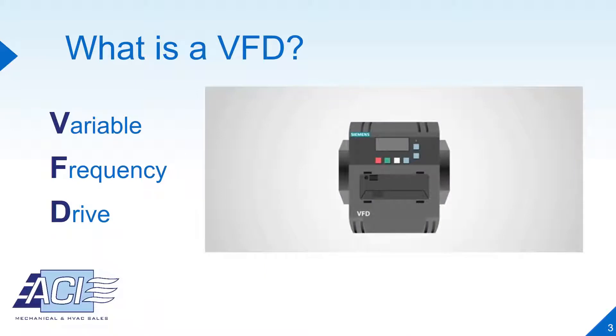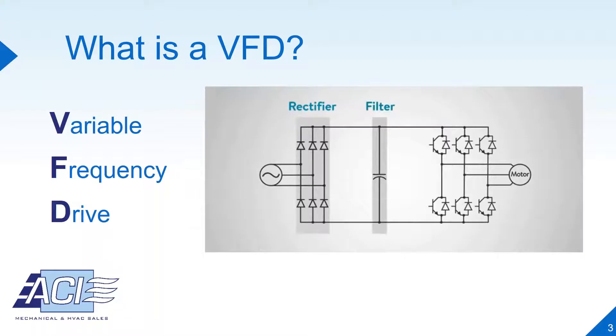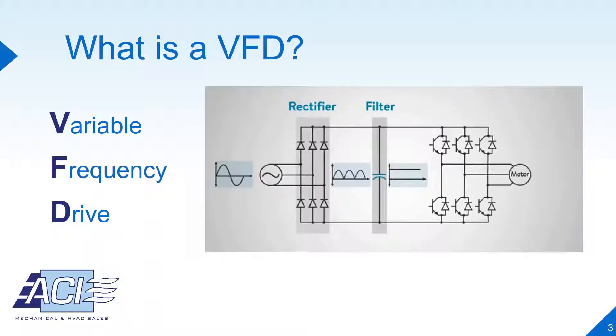What is a VFD? VFD stands for Variable Frequency Drive, and it is an electrical device used to control the rotational speed of an AC motor by adjusting the frequency of the electrical power supplied to the motor. It converts the voltage twice by first converting the three-phase AC voltage to DC through a bridge rectifier consisting of six diodes. Then, the DC voltage passes through the filter, which uses a capacitor to smooth out the signal. Finally, the inverter is used to convert the DC voltage back to AC with transistors acting as switches.